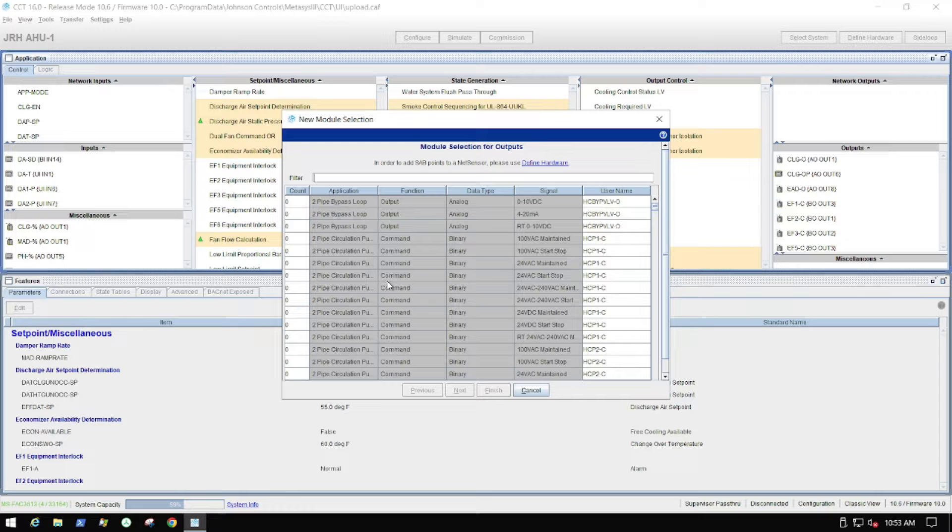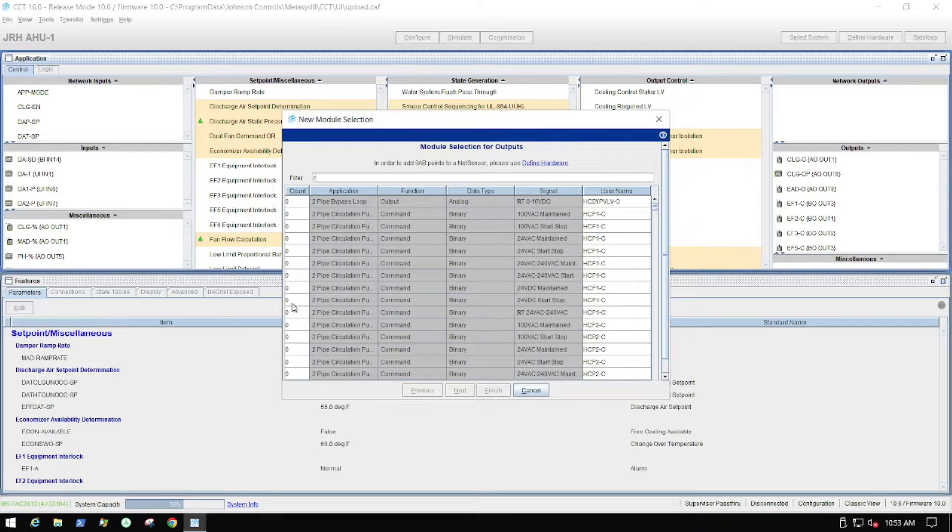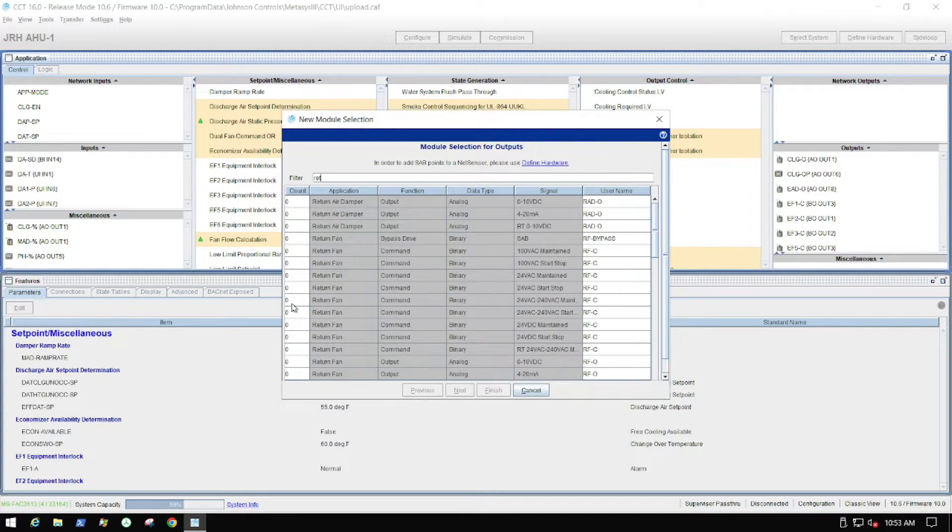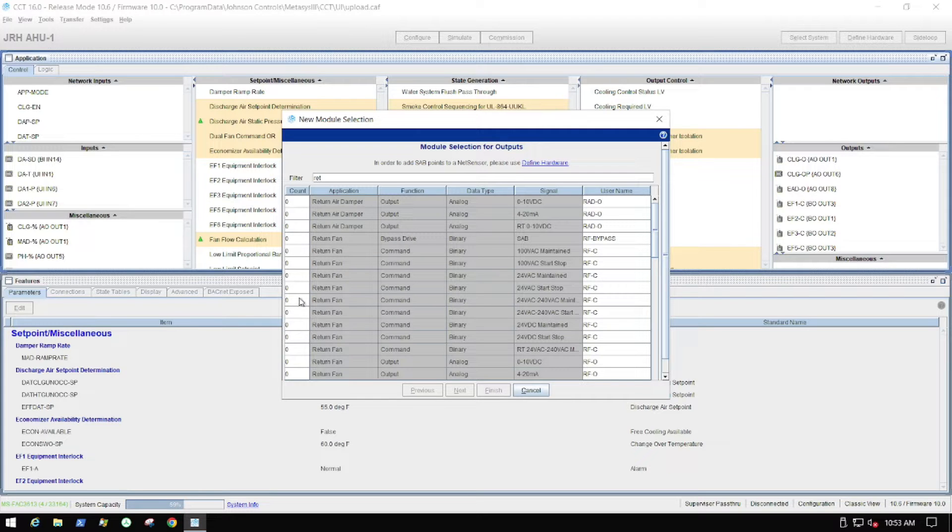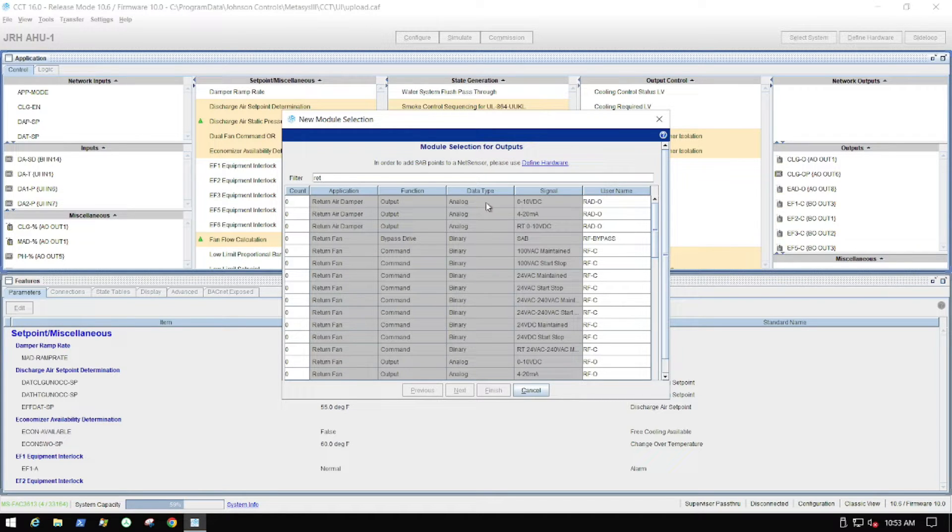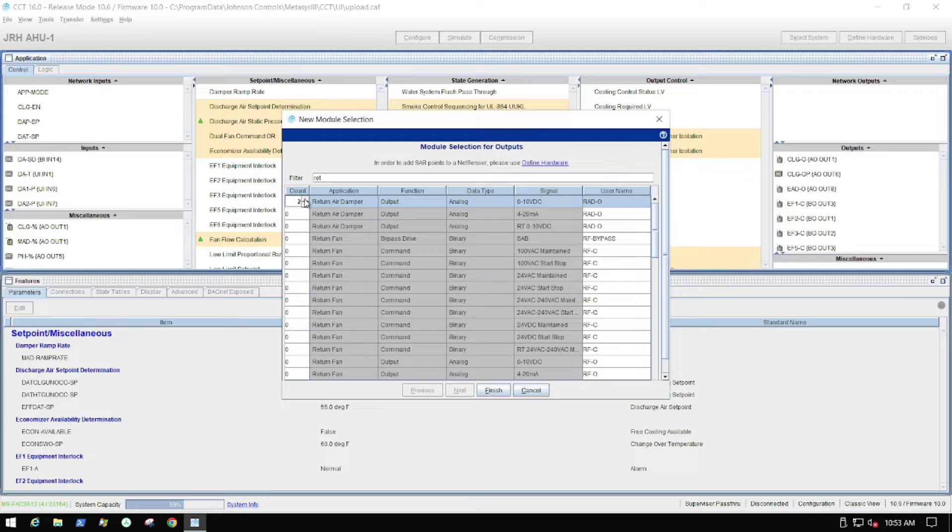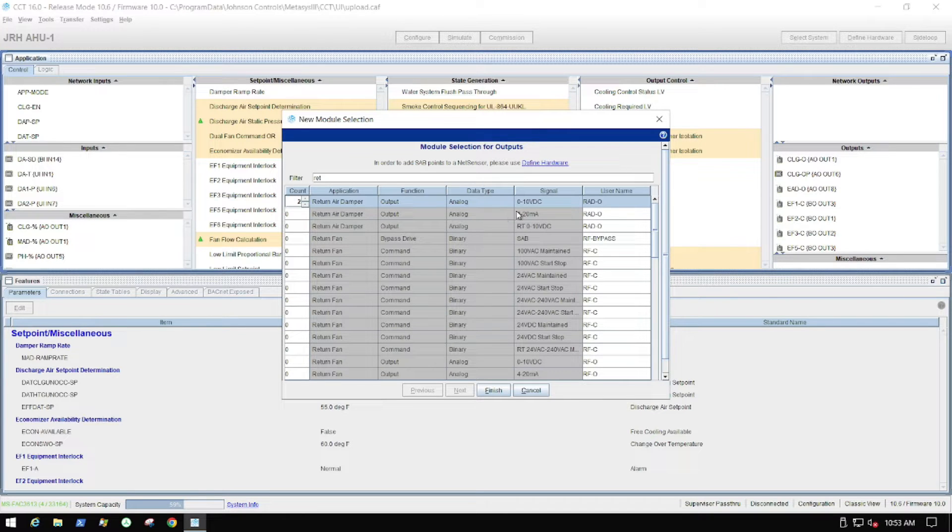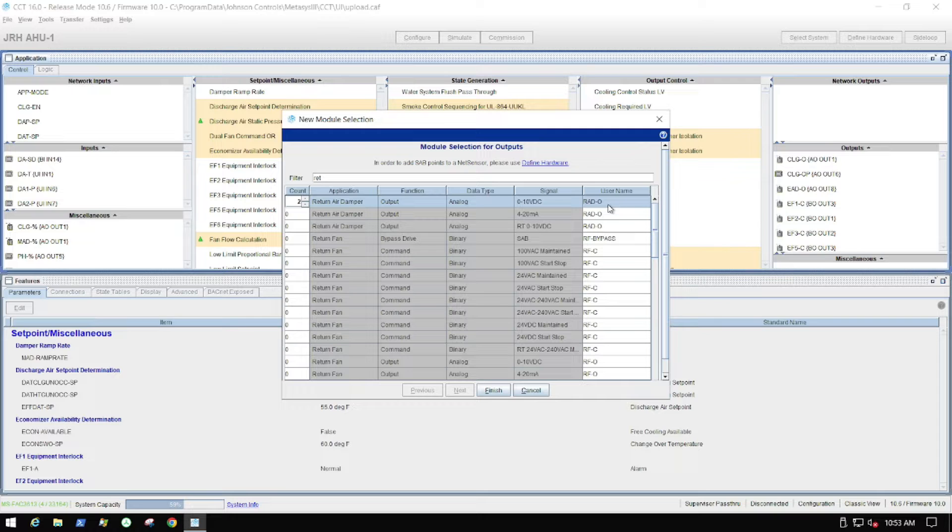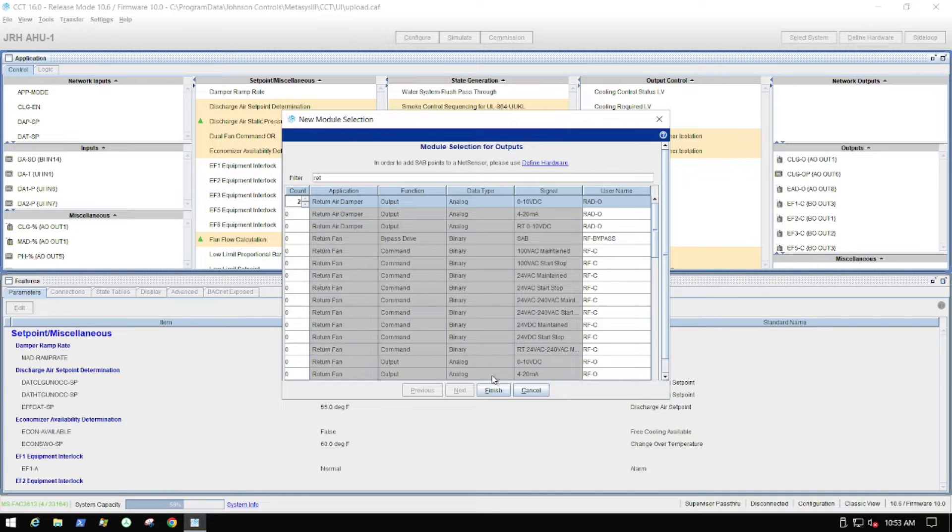So what we're doing here, we have added a remote I.O. to a very large unit and have modified the unit, switching it from pneumatic actuators to an electronic actuator. So we've had to do quite a bit of work between adding power supplies and things like that, as well as remote I.O. that are going to be used to drive the additional actuators. So we've got to add the programming to support that.